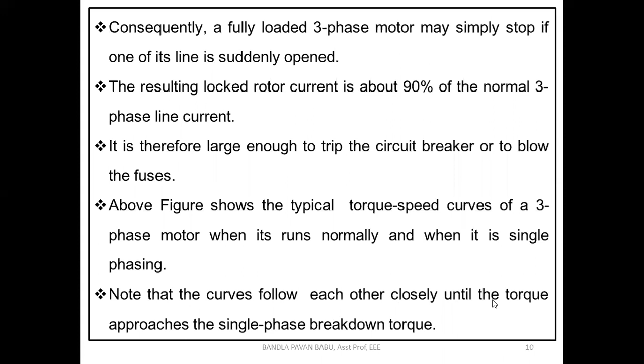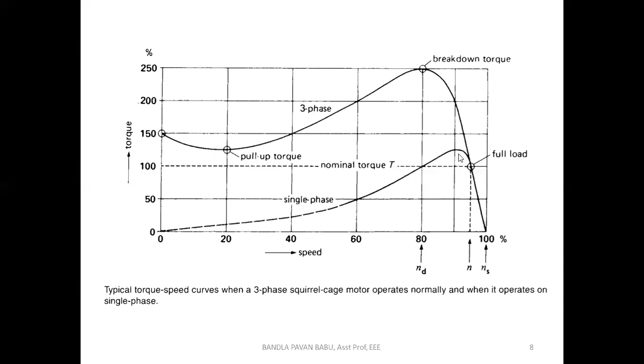The above figure shows the typical torque-speed curve of a three-phase motor when it runs normally and when it is single phasing. As I said before, this is the three-phase induction motor. When one of the phases is removed, it acts as single-phase motoring. What is the torque condition there? What about the current drawn in this condition? Whether the rotor rotates or not, we have discussed all these things. Note that the curves follow each other closely until the torque approaches the single-phase breakdown torque, where it suddenly falls.